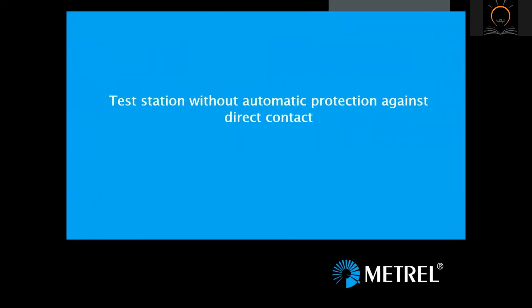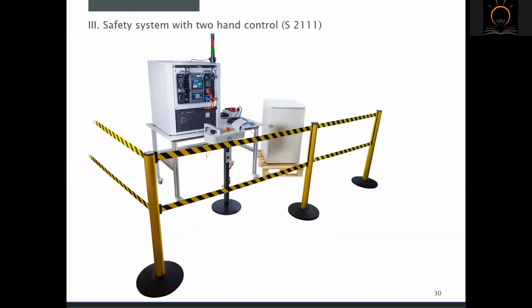Next one is the solution without automatic protection against direct contact. A test station built with a two-hand control safety system is the preferred solution for testing larger objects. When checking the electrical safety of larger electrical devices, PE continuity must be tested on all accessible metal parts. In practice, this means checking the connection of multiple locations on the device. The operator must therefore have access to the device under test at some stage during the electrical safety check to perform the test on every test point.